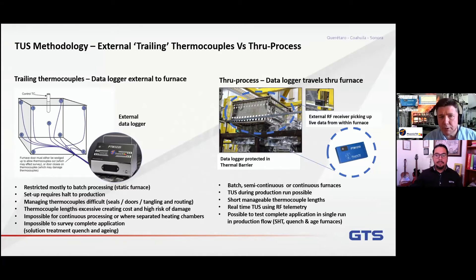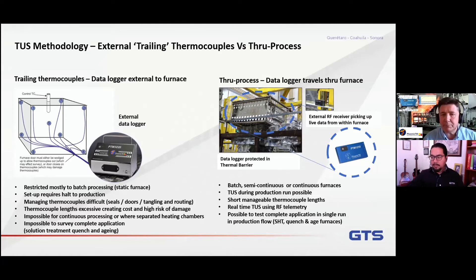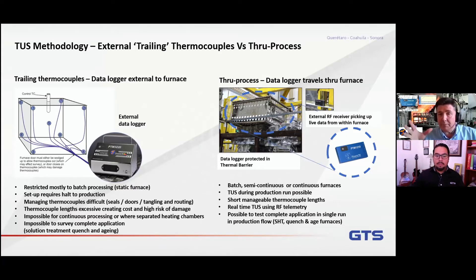That's where the through-process technology comes in. Because the barrier is traveling with the product in the product basket, everything is contained, so it can travel from one section to another without any risk of things getting tangled or caught up. The big question people will ask is, don't I need live data to do a survey? With a trailing thermocouple, that's possible because you're connecting the thermocouple to the data logger and there's generally a display or PC monitor where you can see the data. The through-process technology achieves this using radio telemetry.